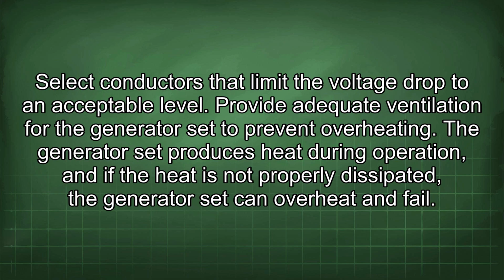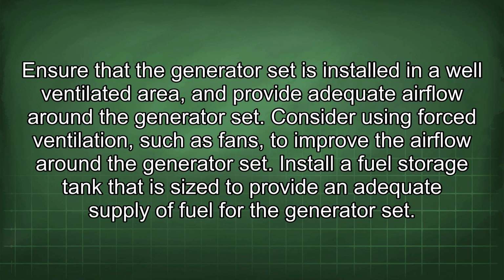Provide adequate ventilation for the generator set to prevent overheating. The generator set produces heat during operation, and if the heat is not properly dissipated, the generator set can overheat and fail. Ensure that the generator set is installed in a well-ventilated area, and provide adequate airflow around the generator set. Consider using forced ventilation, such as fans, to improve the airflow around the generator set.